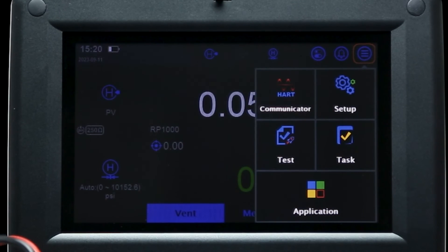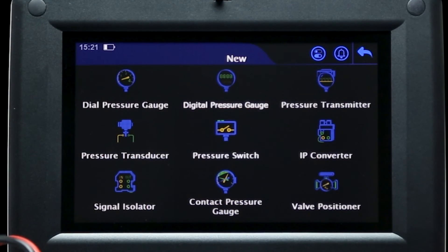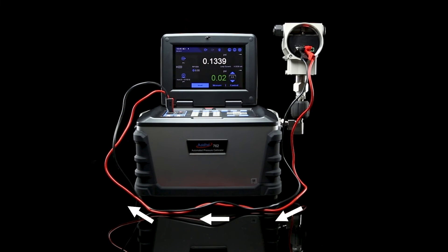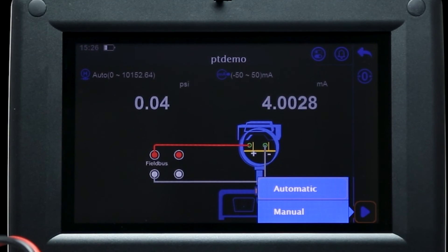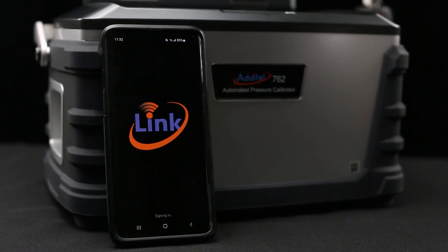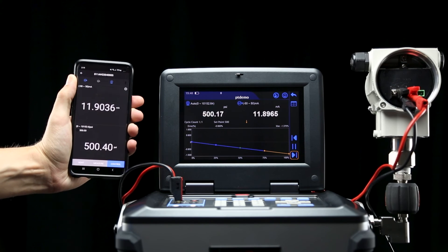Now we will create a task for the transmitter using the same process as we did for the pressure gauge, but instead selecting pressure transmitter from the device screen. Since the transmitter can relay a signal back to the 762, you can now run an automatic calibration at the press of a button. This calibration process can also be viewed remotely using the Additel Link app, which can be connected to the 762 using Bluetooth communication in the settings menu.